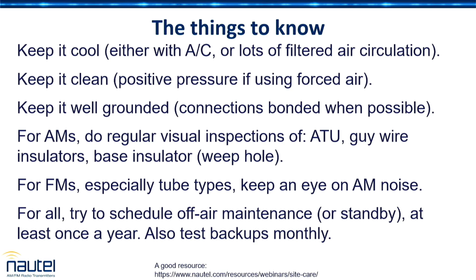Now you hit a point of diminishing returns. You're not going to take the site all the way down to absolute zero, but if you could, you'd have infinite lifespan -- yay -- except it all freezes solid, because things with lubrication in them don't tend to function so well when the lubrication gets thick. So it's a balancing act, but that's the kind of thing to pay attention to.